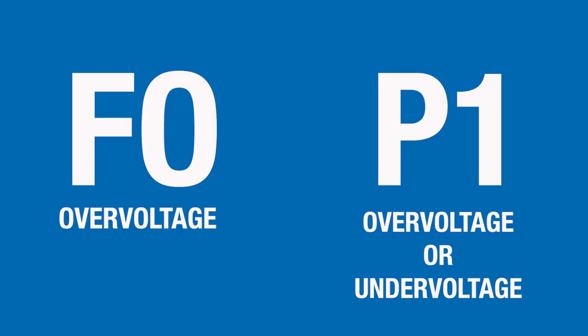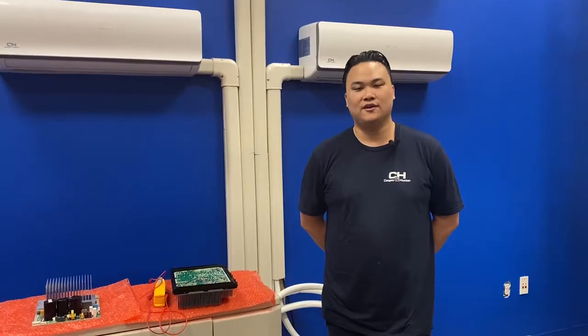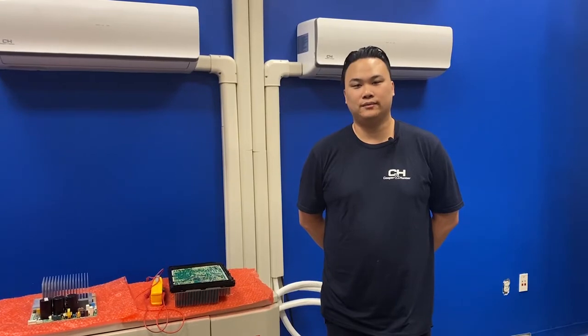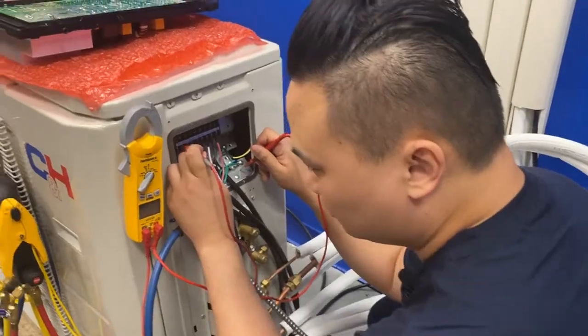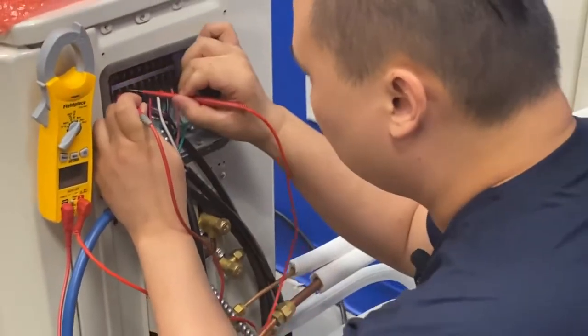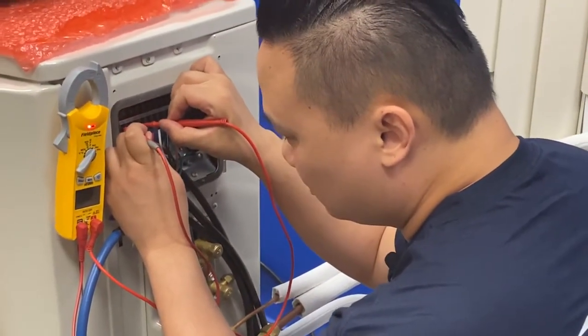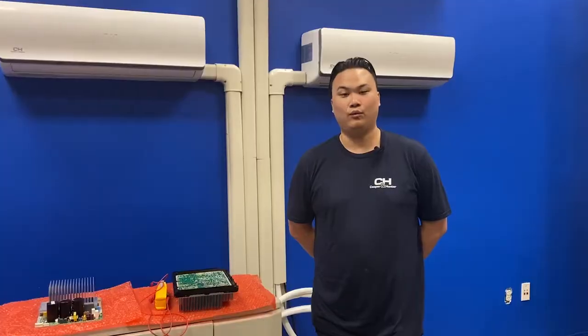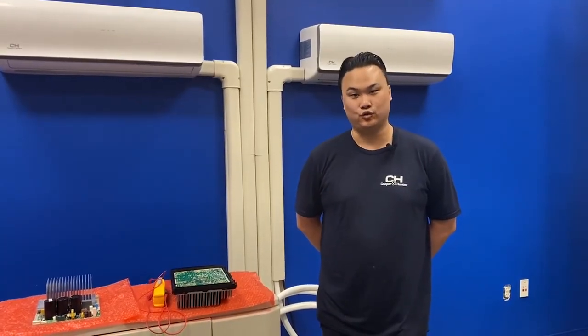If your indoor unit is displaying an F0 error code, that indicates overvoltage. If your unit is displaying a P1 error code, that indicates overvoltage or undervoltage. To troubleshoot these issues, first thing I would do is check voltage coming into the unit. I would check each line to ground, and then each line to each other. If your power is correct, I would start checking the boards to see if there's any shorts on them.